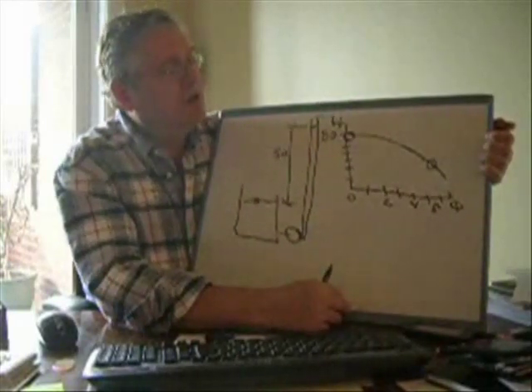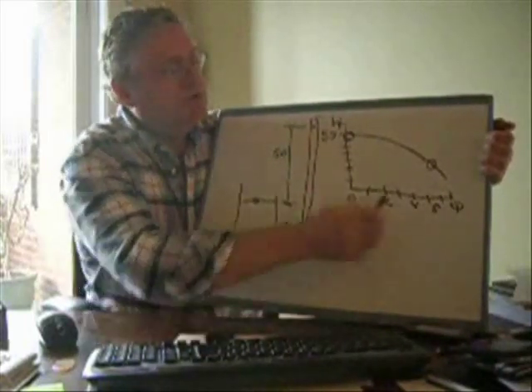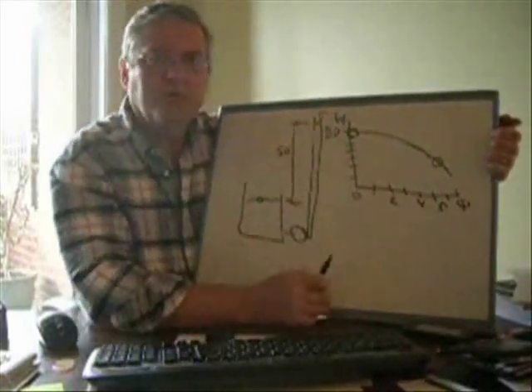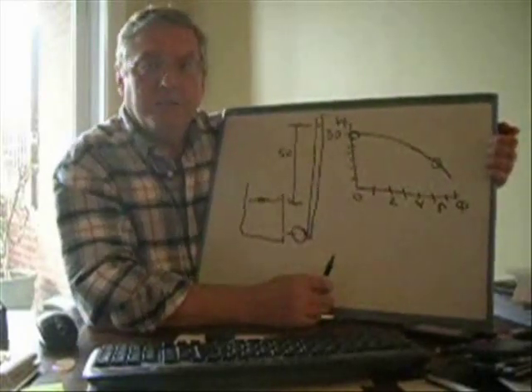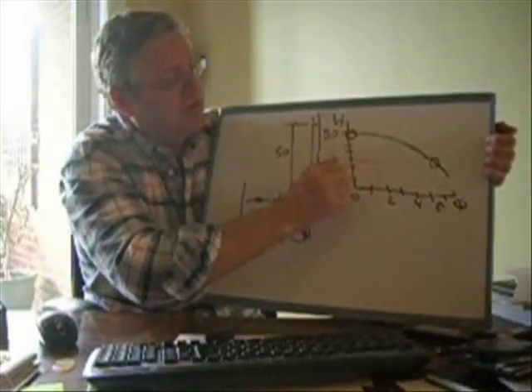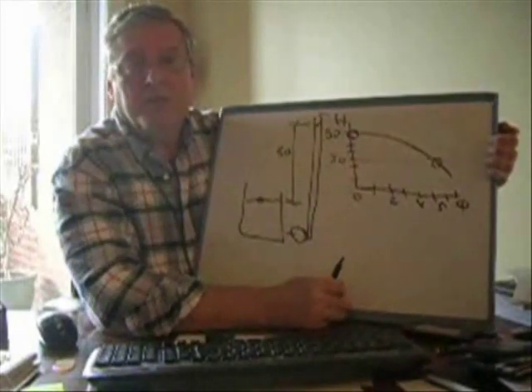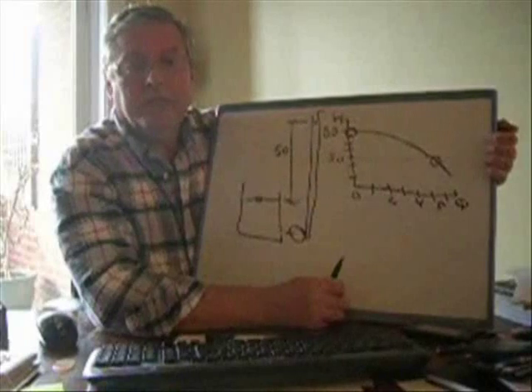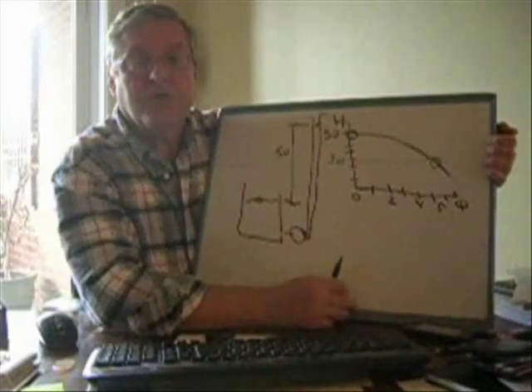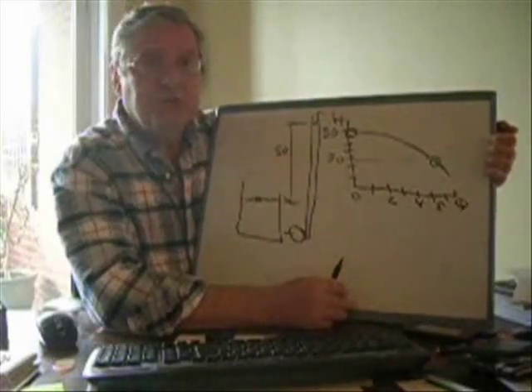The big pump, small pump, medium pump, they all want to do a job with a certain capacity because they are physically built for a certain size. So the pump will itself, so the job of the designer is to find the right pump for the right job. Once we've established that we need so much, so many feet of head at a certain flow rate, we can go to the manufacturer, to the store and say, listen, I need a pump that will do that job. At, say, 40 feet of, say this is 30, 30 feet of head and 70 gallons a minute, I want a pump that will match that operation. And we're probably going to find one. Maybe a little bit bigger than you need, but then you'll just have to close down the valve a little bit so that you don't have way more flow than you need. And that's essentially how it's done.